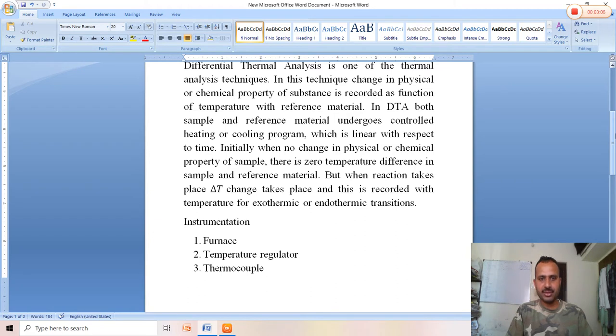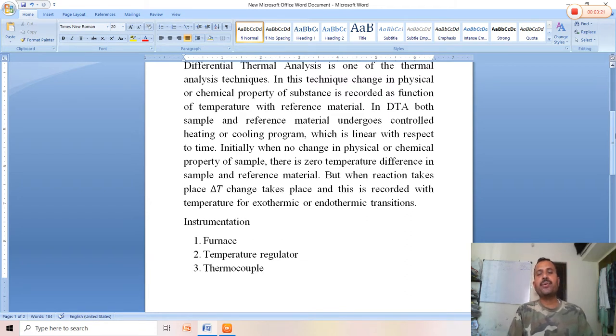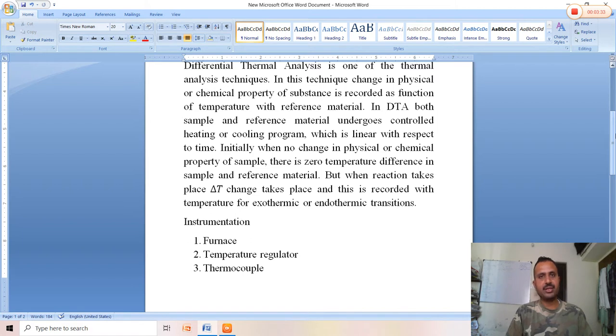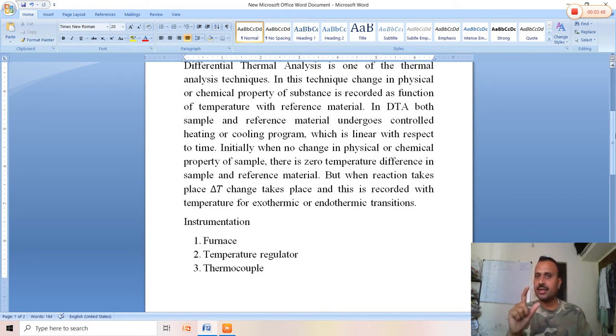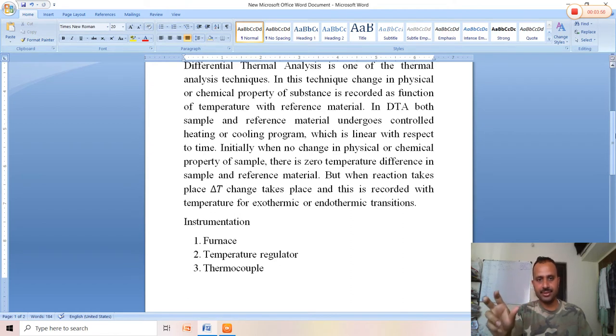We provide heat to the sample and reference material through a heating or cooling program, which is monitored with time. Initially, when there is no change in physical or chemical property of the sample, there is zero temperature difference between sample and reference material — delta T equals zero. But when a reaction takes place as we apply heat using the furnace, delta T changes. This delta T is the temperature of the sample minus the temperature of the reference material, representing a deviation in temperature, recorded for exothermic or endothermic transitions.